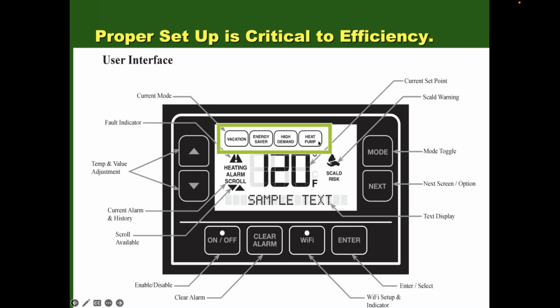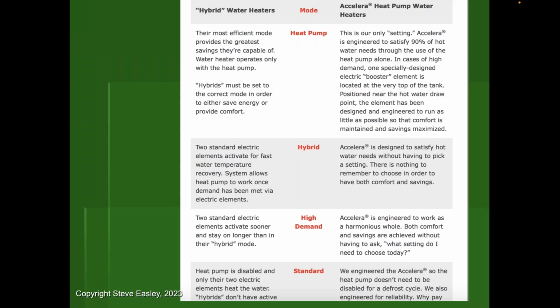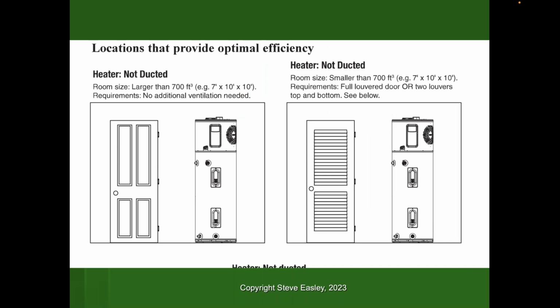You want to have this operate on heat pump mode as much as possible, and second to that, energy saver mode. All the different manufacturers are pretty close to this. I mean, they all have a similar interface. They either run at heat pump mode, hybrid mode, a high demand mode, or standard. You could check whatever manufacturer of your choice, but the bottom line is I run mine in heat pump mode and never had any issues.